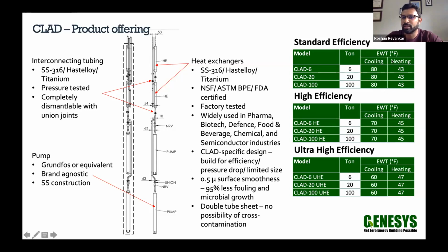On the entering water temperature side, these units are designed to operate between 80 and 43 degrees, 80 on the cooling and 43 on the heating side. We've got two more efficiency models available. These are essentially more heat exchangers within the heat exchanger body itself. And those could operate in much tighter temperatures of 70, 45 and so on.